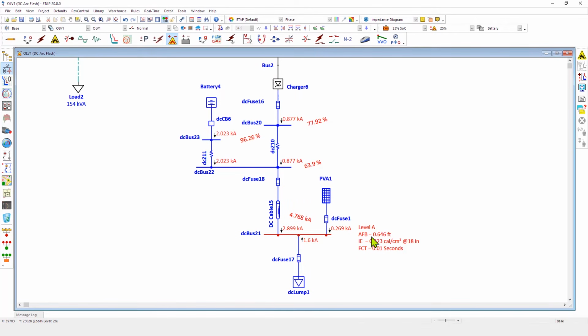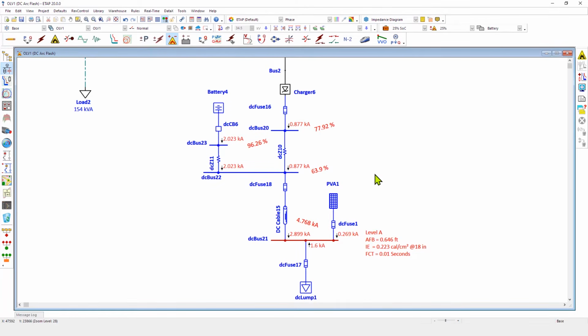Therefore, the maximum impact to the incident energy is due to the increase of fault current and not due to the time delays created by the characteristic curve of the fuse. So therefore, we can observe what happens at different state of charges for the batteries in the system and how they interact and affect each other, and finally how they affect the arc flash boundary, the PPE requirement, as well as the incident energy. Let's switch our attention now to the interaction between the AC and the DC system.